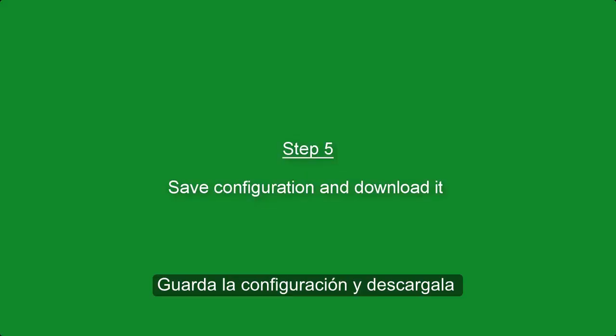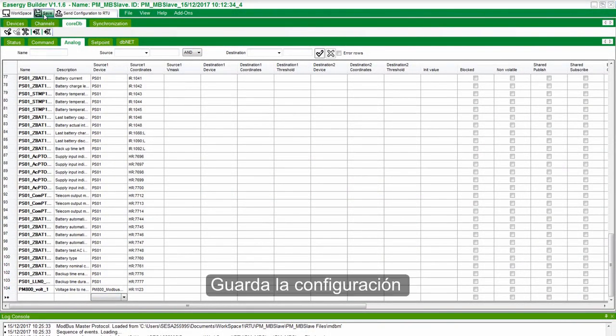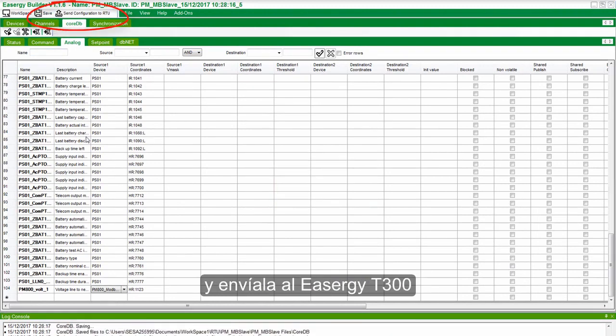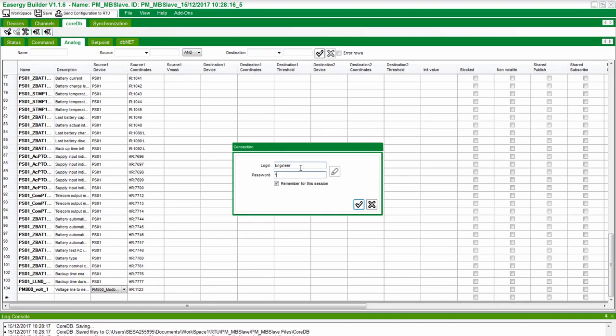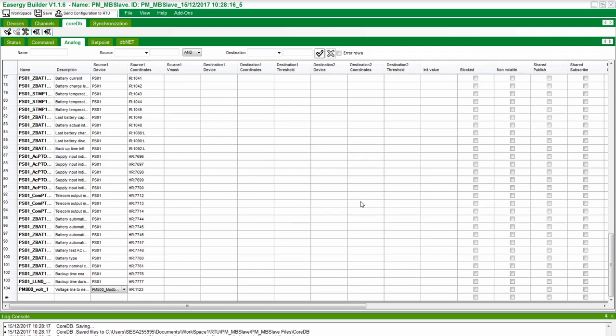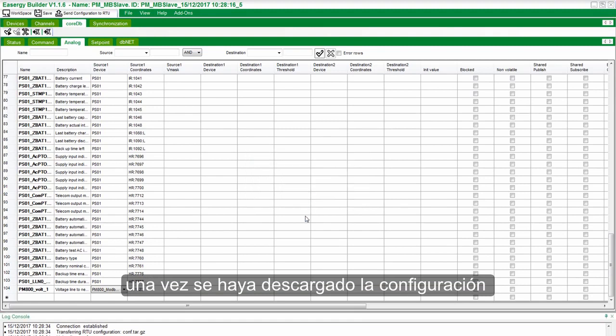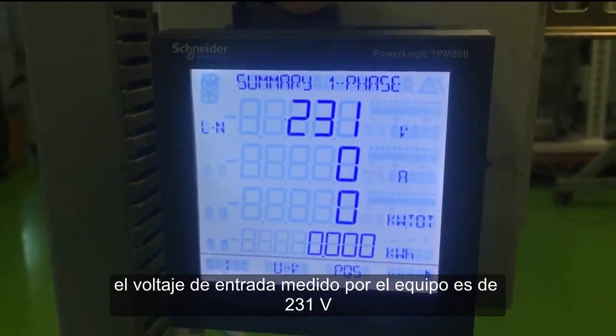Step 5: Save the Configuration and Download it. Save the configuration and send it to the Easergy T300 by logging in with the right username and password. After the configuration is downloaded, verify the data on the device and compare it with the actual value received in the Easergy T300. The input voltage measured on the device is 231 volts.